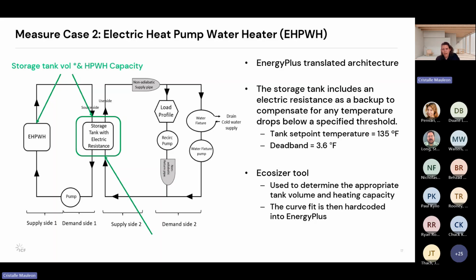One modeling challenge we had here was that Energy Plus does not appear to support a separate swing tank object because it requires every loop to be fully connected and balanced in terms of flow. I have a slide about that later if that doesn't make sense. So introducing a swing tank as a separate object would have required complex flow routing between multiple loops, which Energy Plus couldn't dynamically resolve. So to address this, that's why we combined the swing tank and the storage tank into one with an electric resistance element.